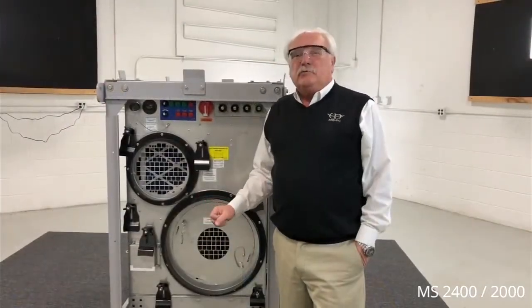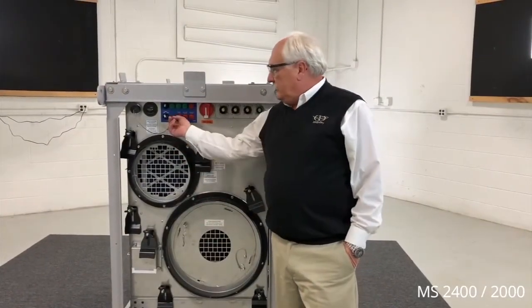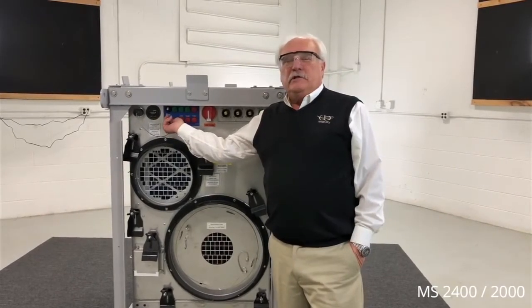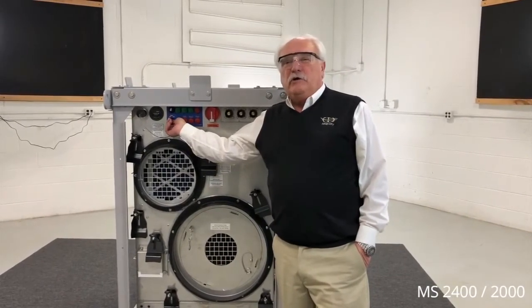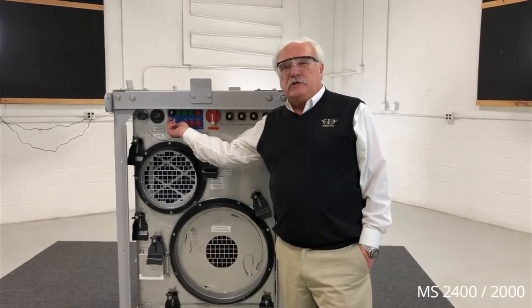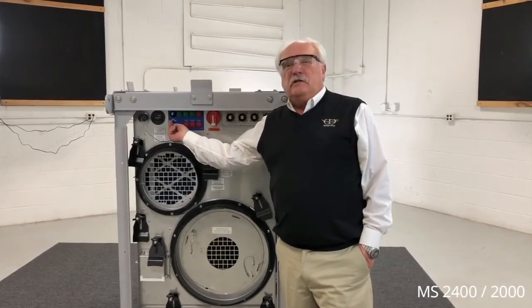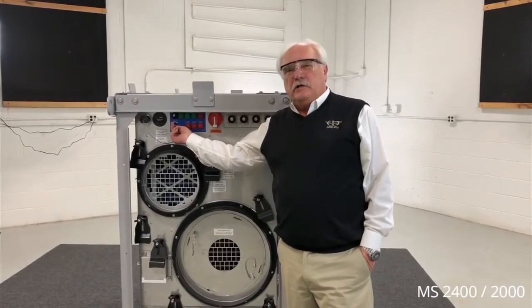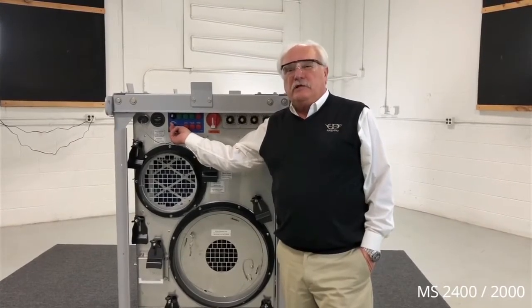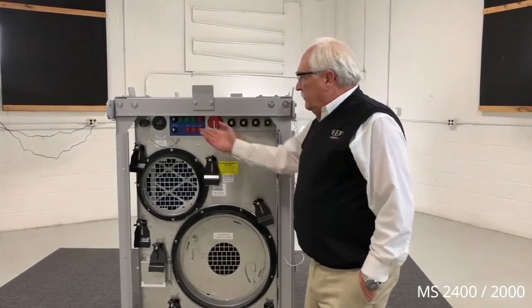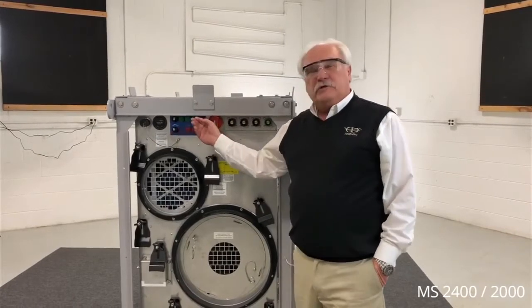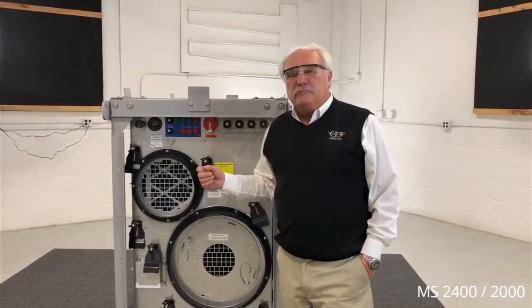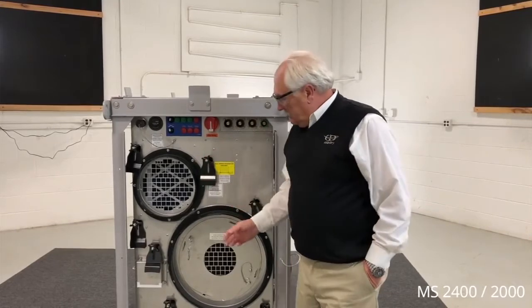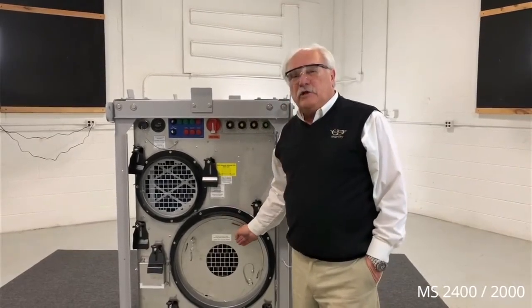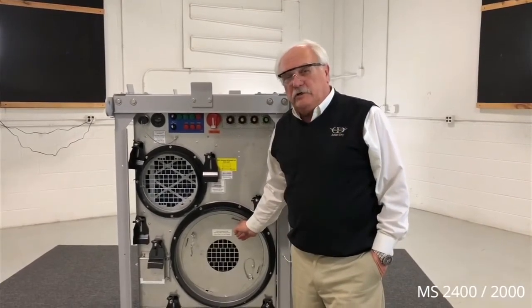This unit is equipped with a high-low rating for the reactivation airstream. The high uses 51.4 full load amps at 460 volt 3-phase. On the low setting, it uses 29.2 amps for reactivation energy. If you're going to use the low setting, we need to restrict the airflow for the process and reactivation airstream, so we include 2 restrictor plates for use during the low reactivation setting.